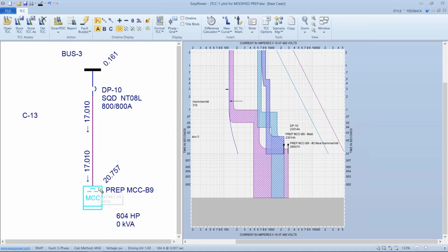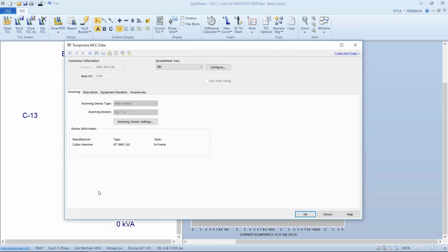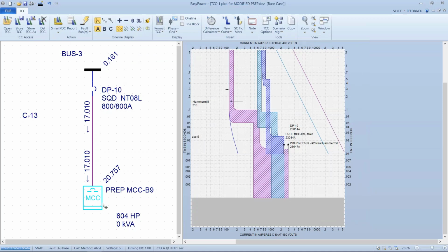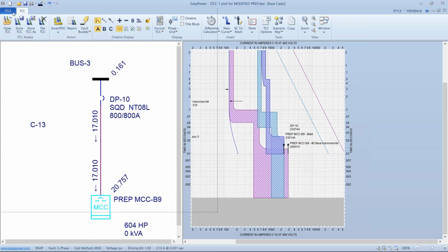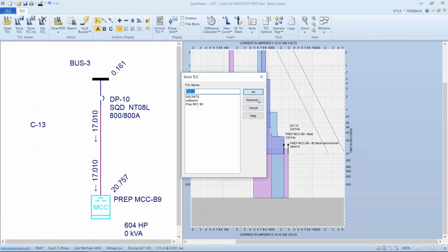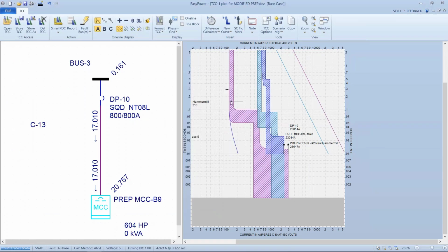Well, the problem here exists because we can't isolate the motor. What we're faulting here is the bus upstream of the motor, and so the first breaker upstream of this bus is not the individual breaker for the motor. It's the main circuit breaker for the whole panel, the whole MCC. And so that brings us back to, if we close this plot, let's go ahead and save changes. Let's not do that. We will in a second.